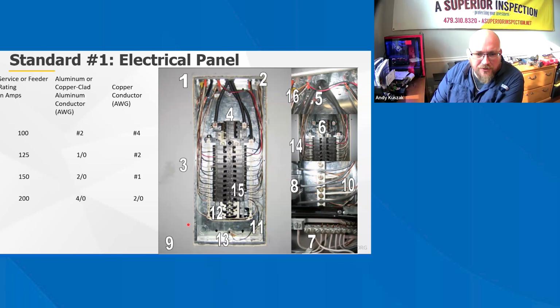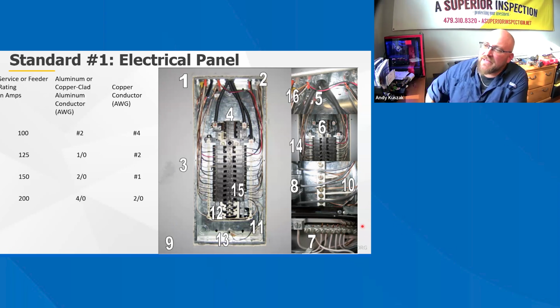Then we're going to number 9, which is down here in the bottom, which is actually blocked by my Zoom stuff. But number 9, a grounding electrode is a device that makes an electrical connection to the earth. A grounding electrode can be rebar in a footer, copper underground water pipe within 10 feet of contact with the earth, or a grounding rod.